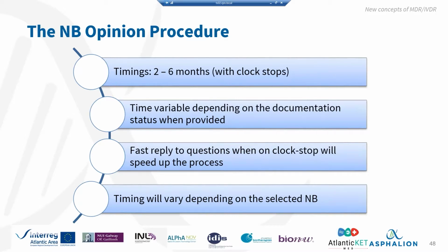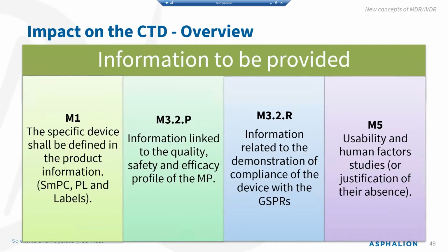Okay. So besides this notified body opinion, what impact does this article have? Well, what this article is saying is that there's a lot of information on the device that has to be placed in the common technical dossier of the medicinal product. If you're familiar with the structure of a CTD, you have several modules, so you've got to include information on the device in these sections listed here: in module 1, in 3.2.P, in 3.2.R, and in module 5.